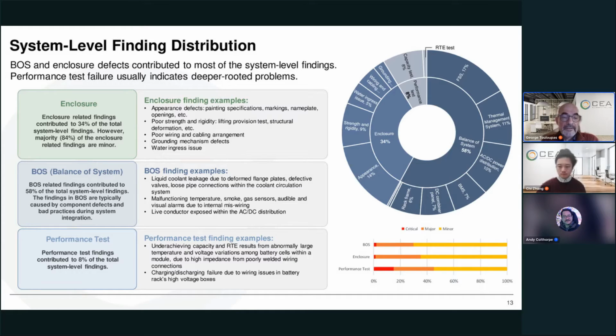The next broader category is the balance of system. Here we have observed liquid coolant leakage. We're gonna see a lot more details about that, but this is definitely super concerning because you need the liquid for the coolant, and second, the liquid next to electrical equipment is a really bad thing. Also, sensors and several mechanisms and alarms are not always installed perfectly, and they might not be working as expected. Even conductors are not insulated properly. So again, live conductor is a very concerning finding.